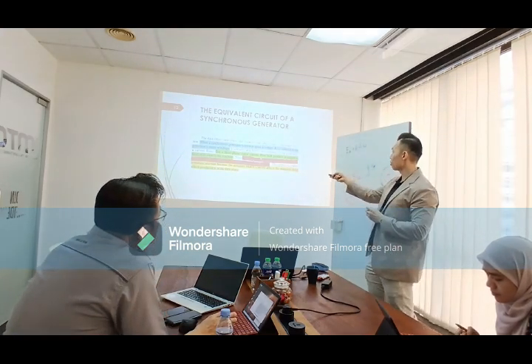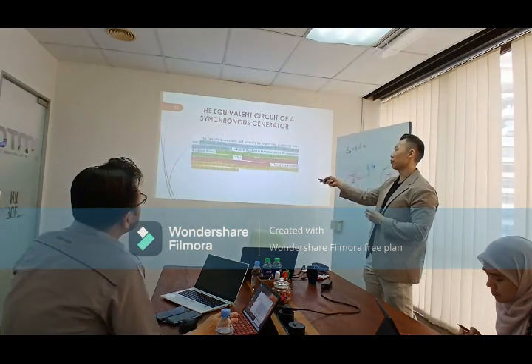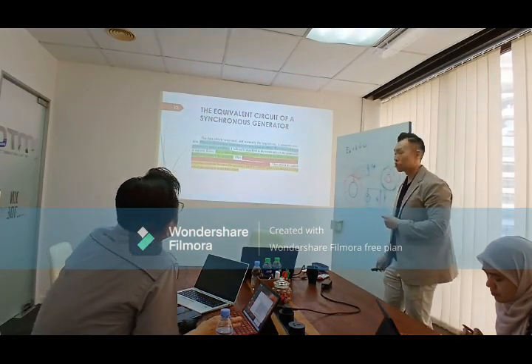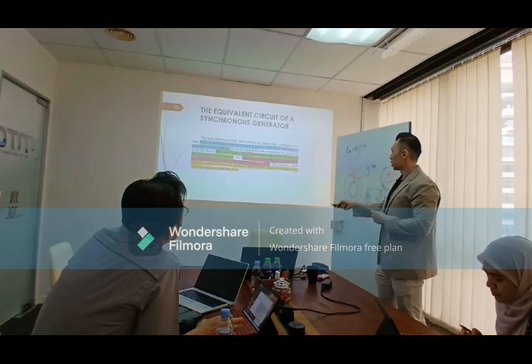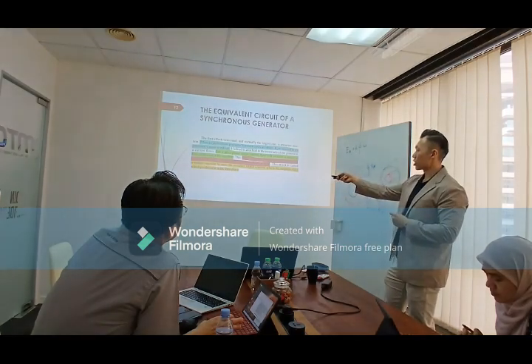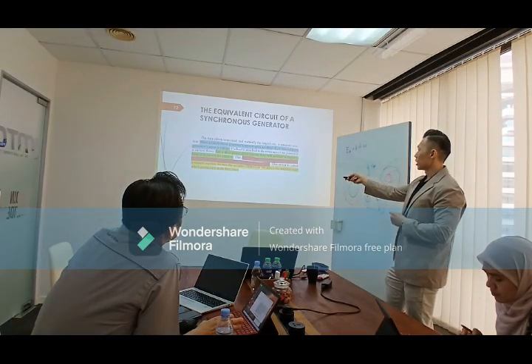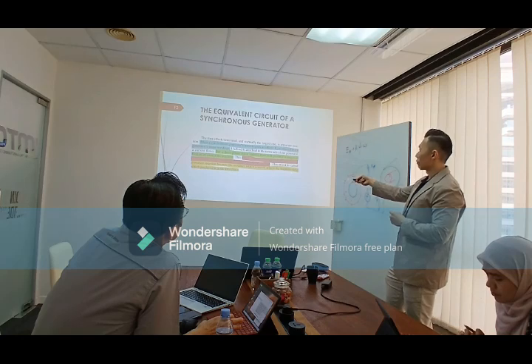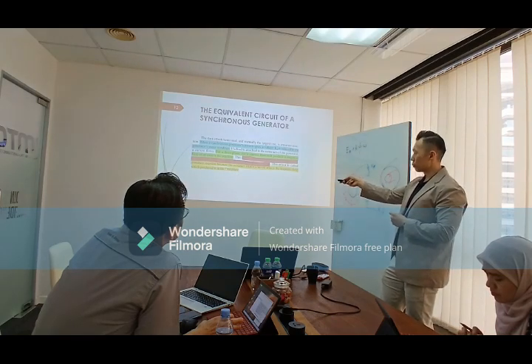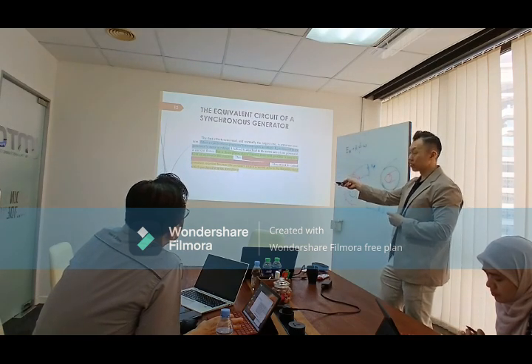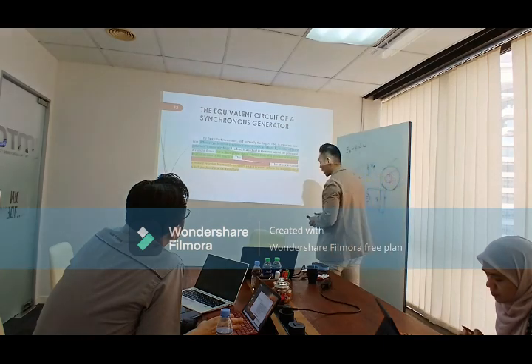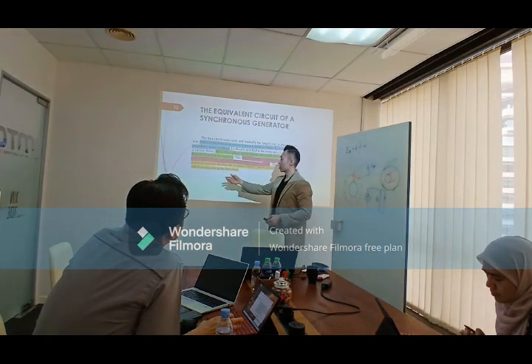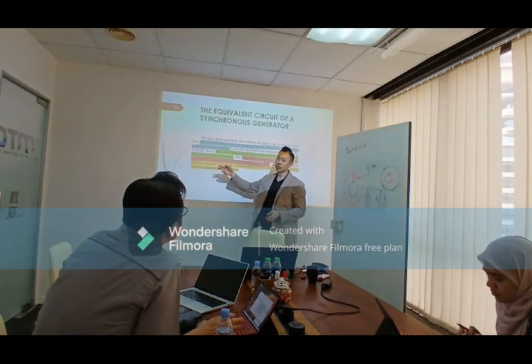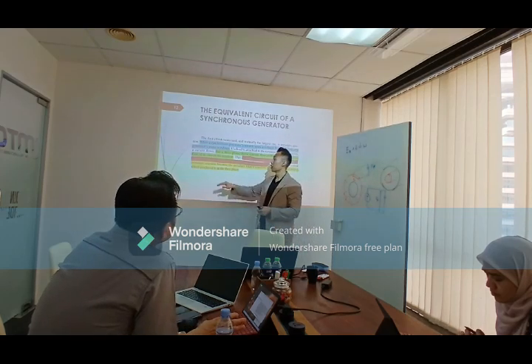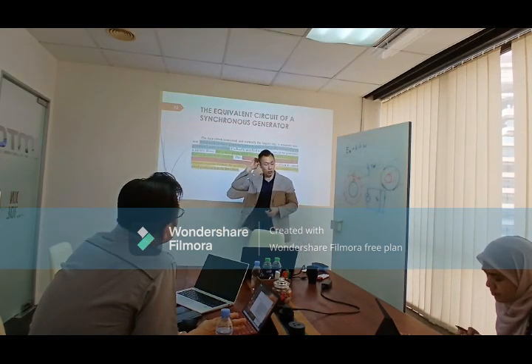So the stator magnetic field distorts the original rotor magnetic field, changing the resulting phase voltage. This effect is what we call armature reaction, because the stator current affects the magnetic field which produced the stator current in the first place. We have a way to counter armature reaction — we normally deploy damper windings to counter this.